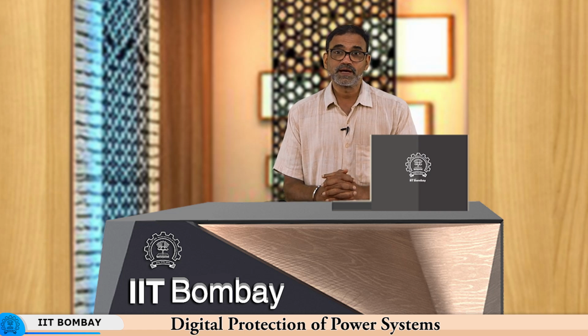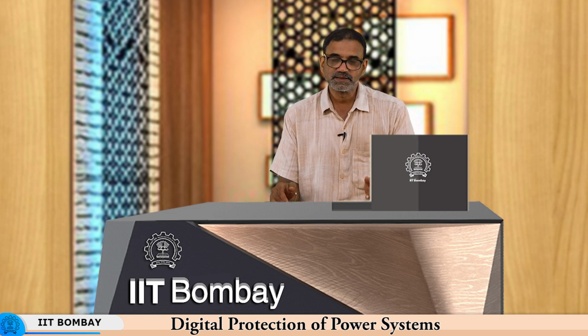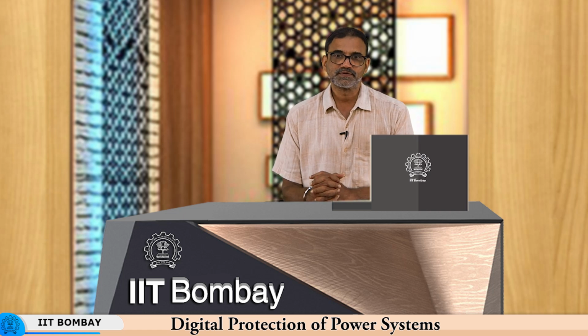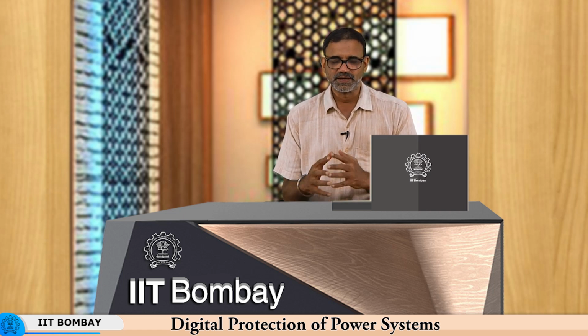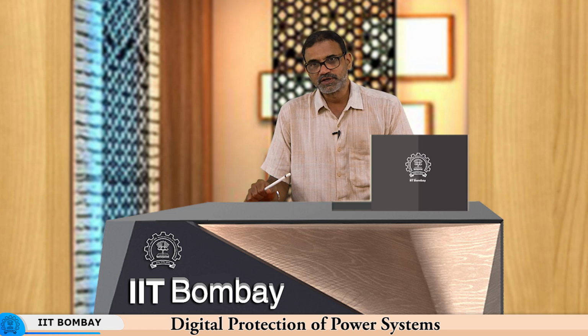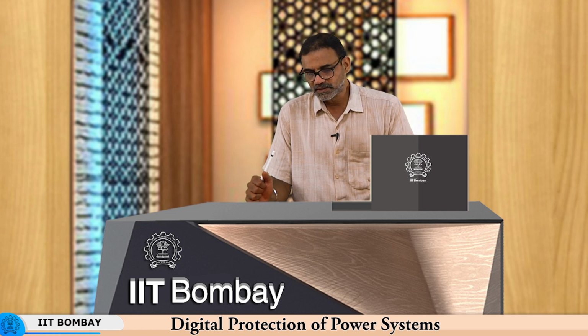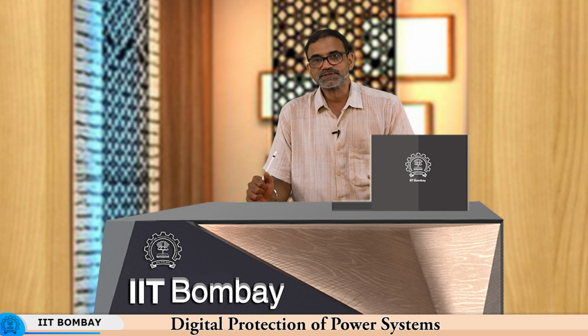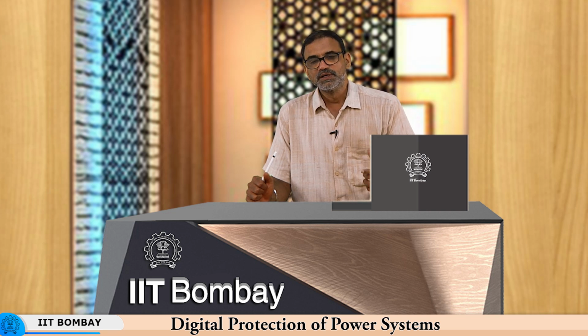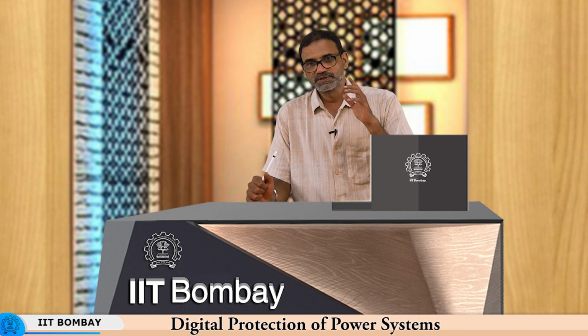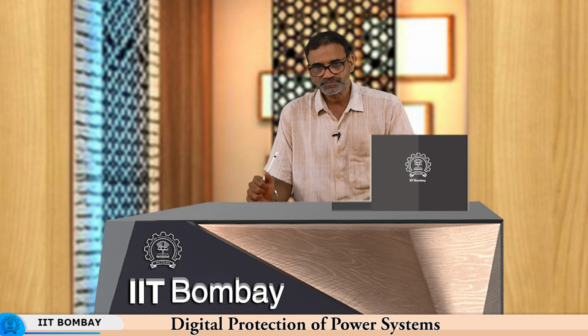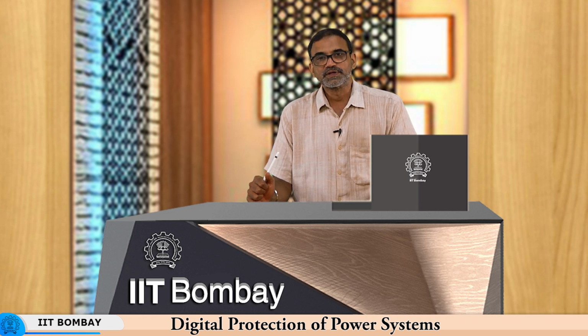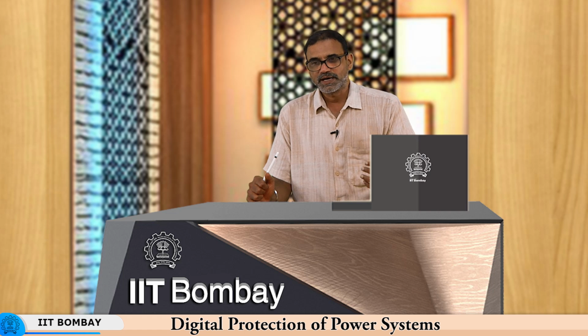With electromechanical relays, or even static relays, there was no way to download data from the relay and replay or use it for post-mortem analysis. You needed other devices known as fault disturbance recorders, which worked only to record data - they were not relays. So you needed an FDR, fault disturbance recorder, with a very high sampling rate so it could track transients, and then you could download some data from that.